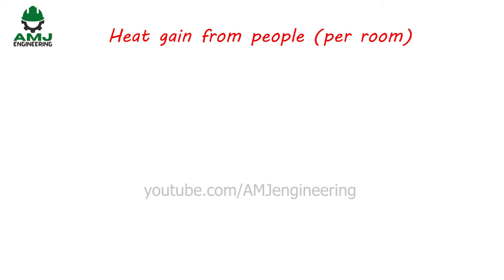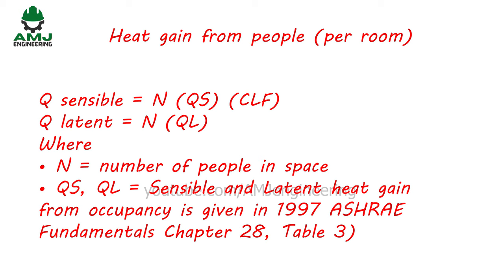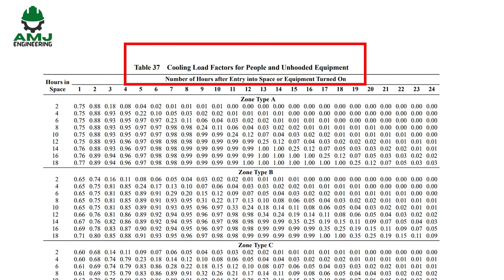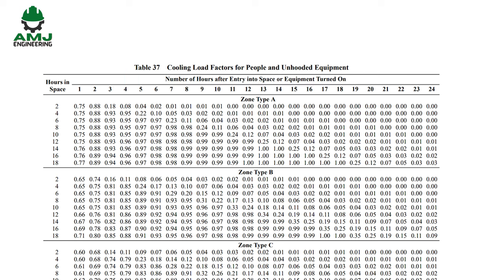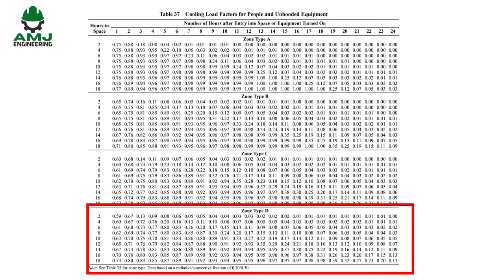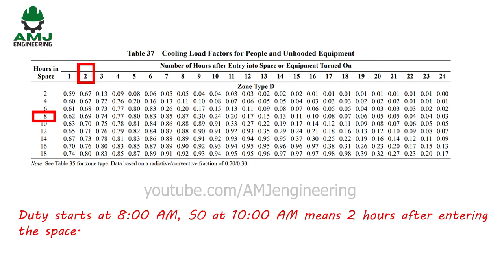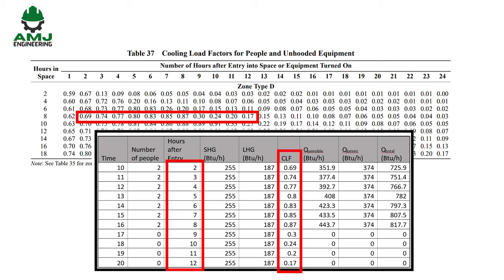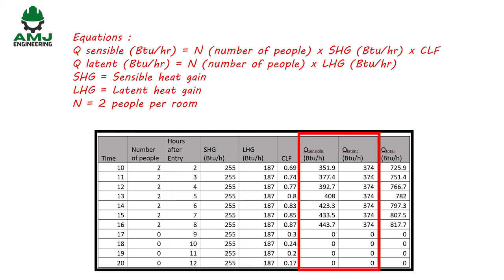The next step is to calculate heat gain from people using: Q_sensible = N × QS × CLF and Q_latent = N × QL. For moderately active office work, sensible heat per person is 75W (255 BTU/hr) and latent heat is 55W (187 BTU/hr), from Chapter 28 Table 3. CLF is the cooling load factor by hour of occupancy, from Chapter 28 Table 37, for Zone Type D. For 8-hour duty, CLF is read based on hours after entering the space. Sensible and latent heat gains per room are then calculated along with their total.